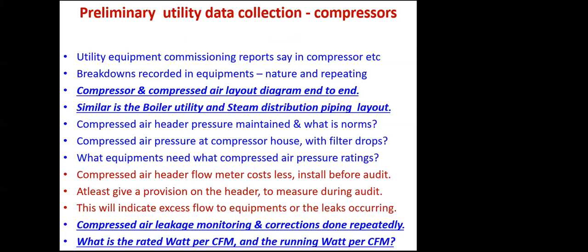Not only on the compressor, it can be used in blowers also. These can all be fitted at the right place, and the point of installation is very important. If it is installed on the compressor header, then when the auditor is here, we know how much CFM is generated by the compressor at what pressure. Normally, a compressor is purchased for 8 bar pressure and it is operated at 6 bar because the package power is more than that, with a service factor of 1.2 for the given compressor motor.